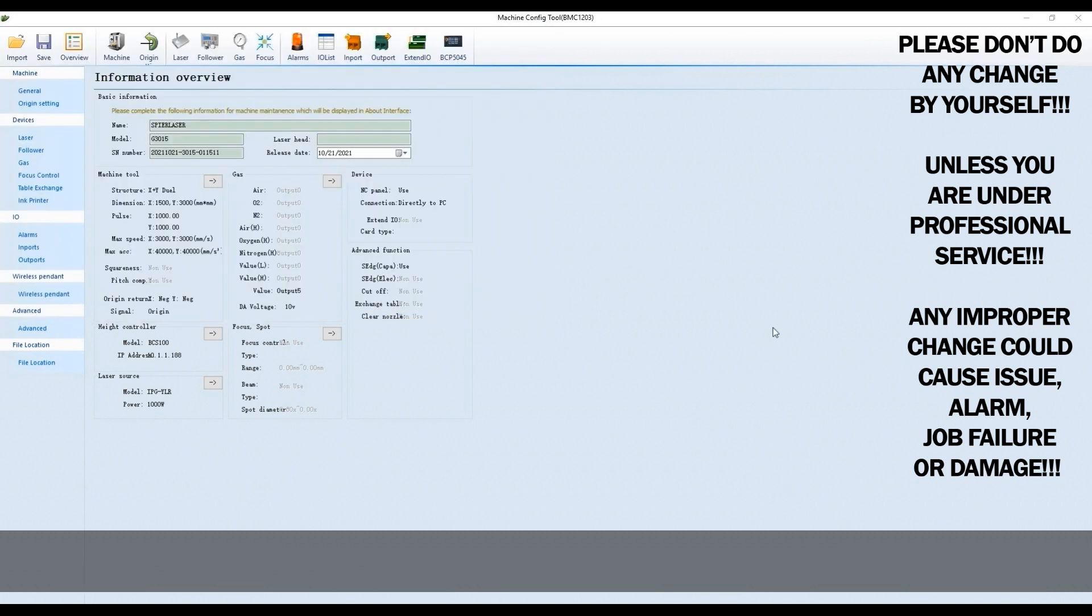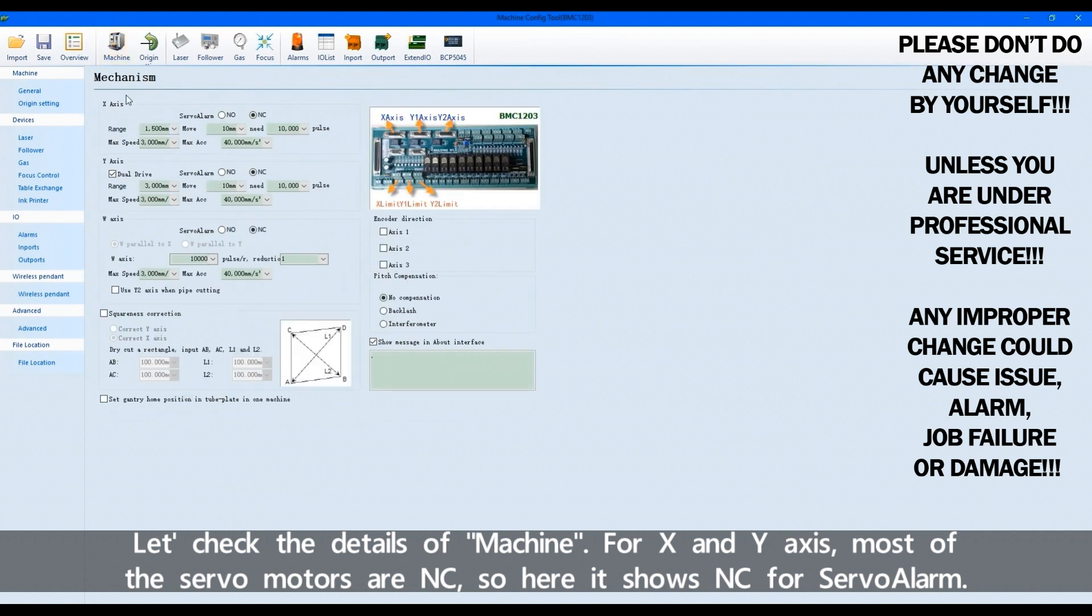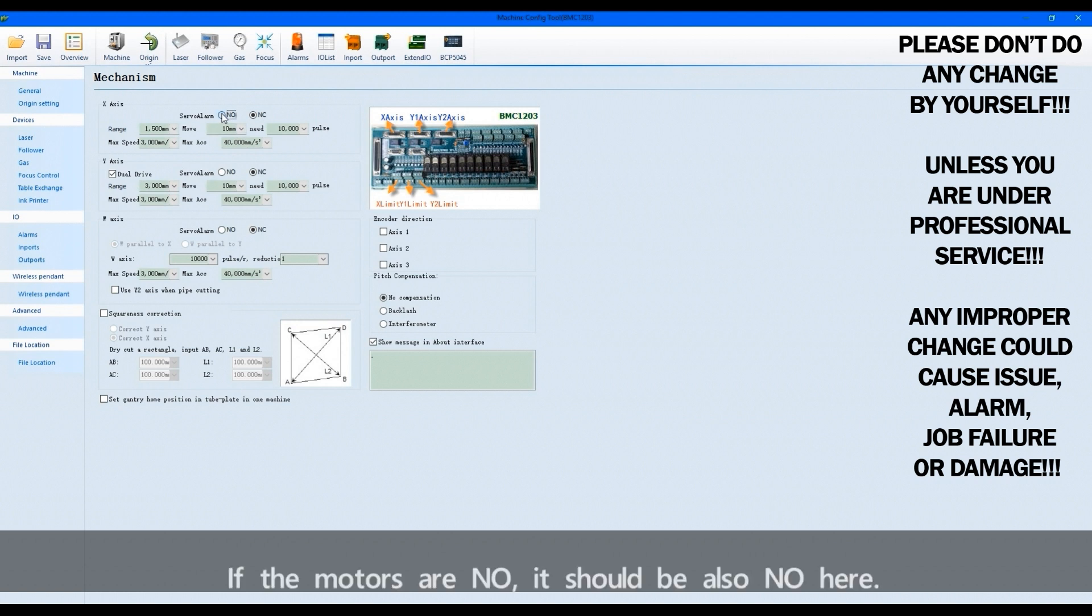Let's check the details of machine. For X and Y axis, most of the servo motors are NC. So here it shows NC for servo alarm. If the motors are NO, it should be also NO here.